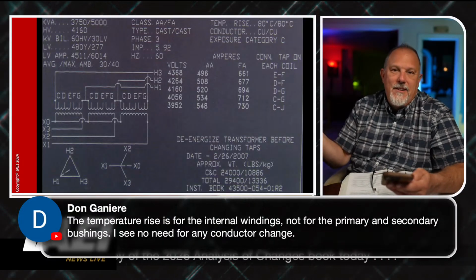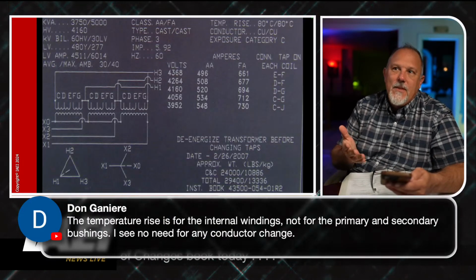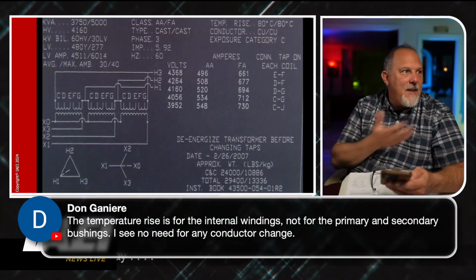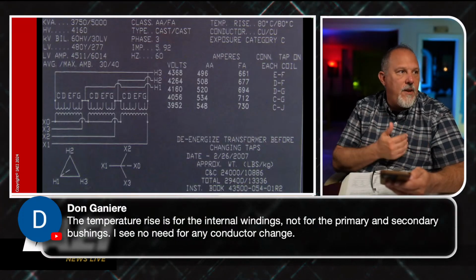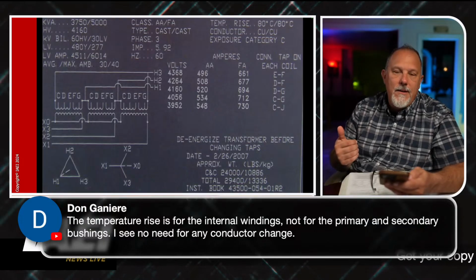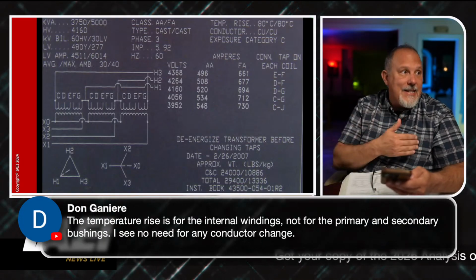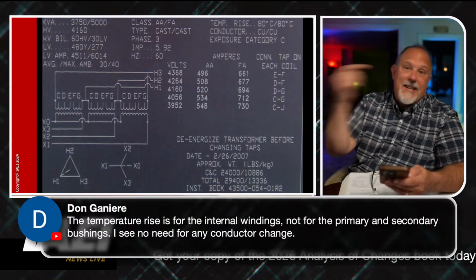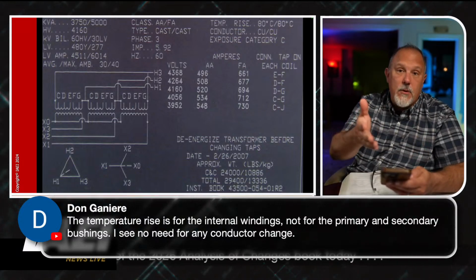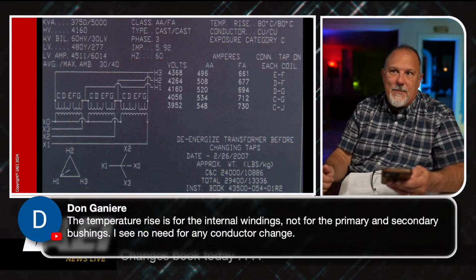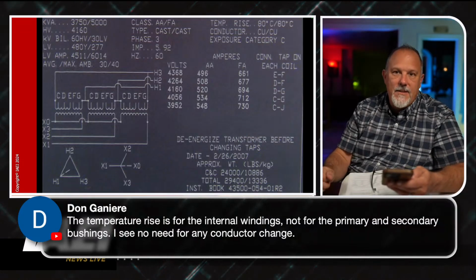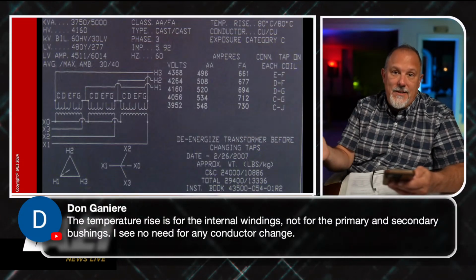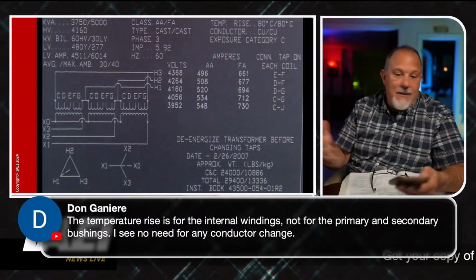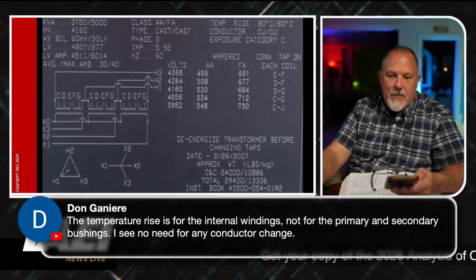You have to. If you have 5,000 kVA and my secondary full load amps goes from 4511 to 6014, and I'm protecting the conductor at 4511, or say 4,000 amps, I'm never going to get the 6,000 amps on the secondary. So I would have to, Don. You would have to. I think you're wrong. That's just my opinion.